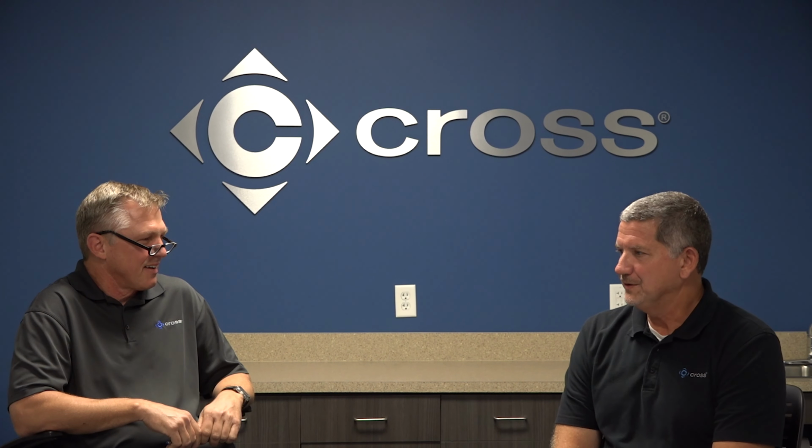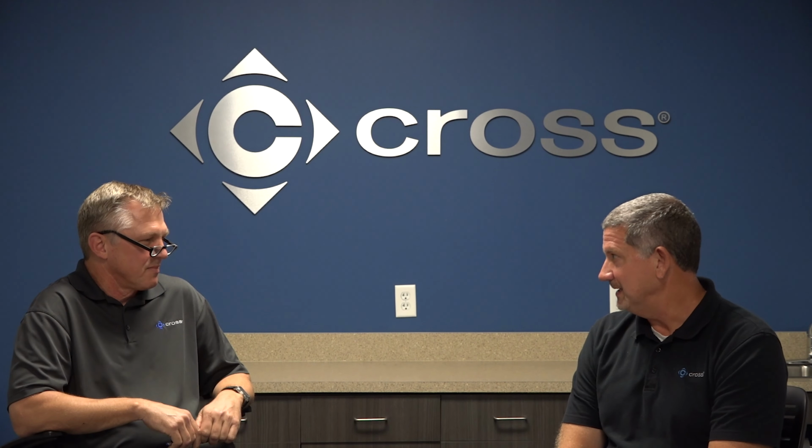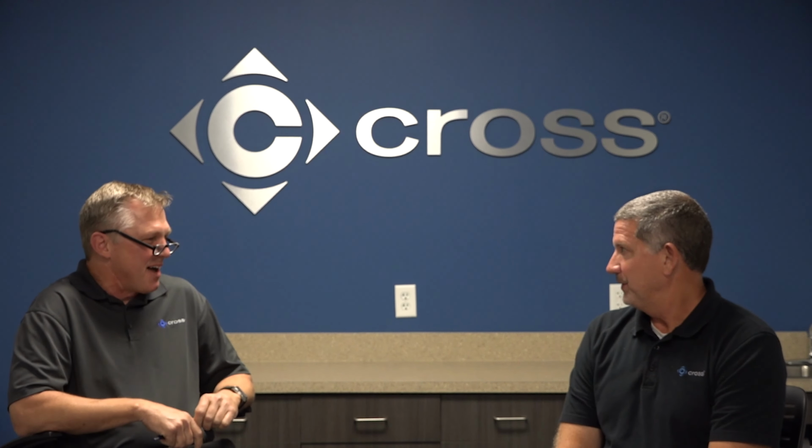A couple of sites that I went to, I had actually seen a safety relief valve that was plugged, to where they had actually put a pipe plug in it because it was leaking. So that device would not function as intended. It's not going to work. There's no protection. I think I'm protected, but I'm not.